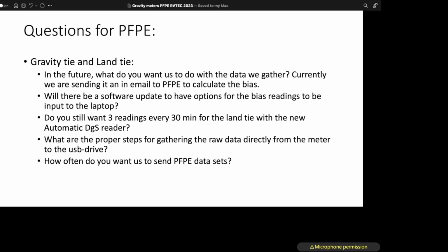Sorry. Oh, that was just initially when we first installed the DGS, you're talking about sending every day, at the end of the day, all the data. And so I think we've changed that now. Yeah. And I think you and I discussed it, but we were talking about sending snippets of part of a transit so that you guys can still see the data, and if that's still right. For the sake of monitoring these meters, it is okay to, for example, wait for data to go to R2R, but because like I said earlier, the meter's behavior has still unknown components for the duration of more than a few weeks or months, we prefer to get the snippets of data, particularly during the transit, if you have.